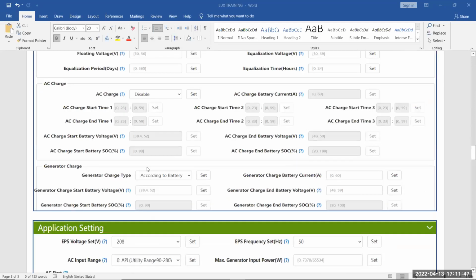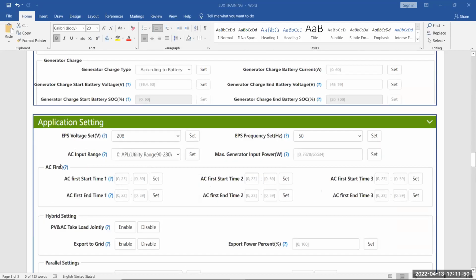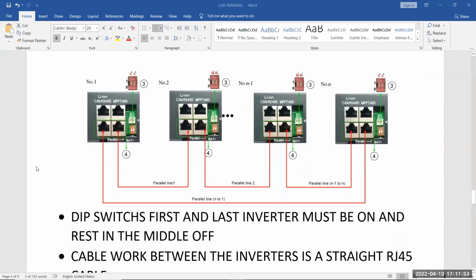Now, one thing is your parallel settings. This is quite some headache for some people, but if you understand it, it's not that difficult. This is a parallel system with 4 inverters in single phase parallel. 3 phase will be exactly the same, only with 3 inverters. Your communication cables between your inverters are straight communication cables. That means it's 1, 2, 3, 4, 5, 6, 7, 8 on the one side, and it's the same through to the other side. Your pins are not crossed over on your RJ45 cables. So for parallel, you're going to start with your master inverter.